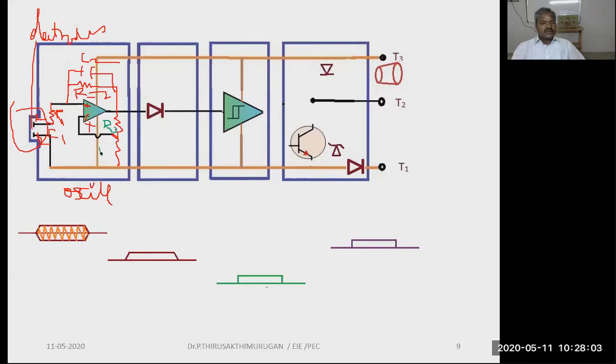This is R4. When there is no object, no voltage is generated by the oscillator. That is zero voltage. When the object is away from the sensor head, there are no oscillations. You see, this is the region where the object is not present at all. So that is the object. When the object is away from the sensor head, no oscillations are generated by the oscillator.